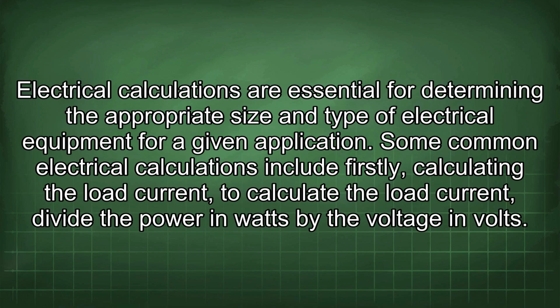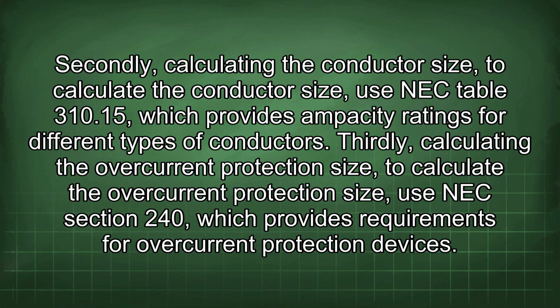Electrical calculations are essential for determining the appropriate size and type of electrical equipment for a given application. Some common electrical calculations include: firstly, calculating the load current. To calculate the load current, divide the power in watts by the voltage in volts. Secondly, calculating the conductor size. To calculate the conductor size, use NEC Table 310.15, which provides ampacity ratings for different types of conductors. Thirdly, calculating the overcurrent protection size. To calculate the overcurrent protection size, use NEC Section 240, which provides requirements for overcurrent protection devices.